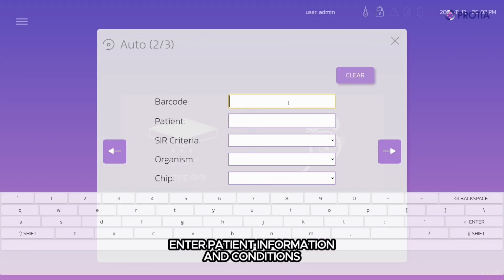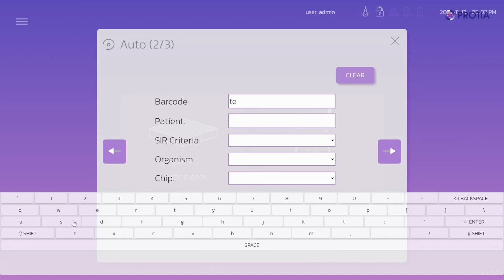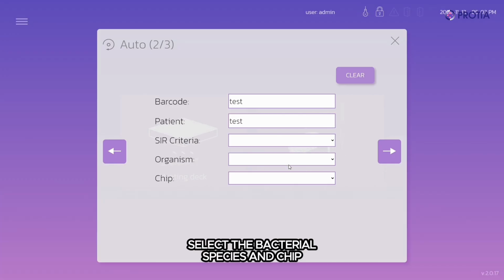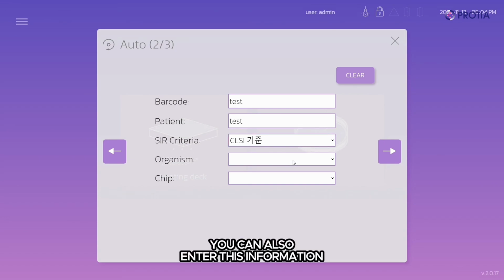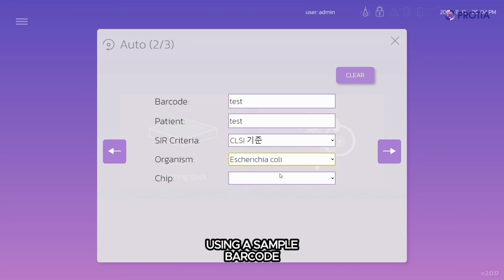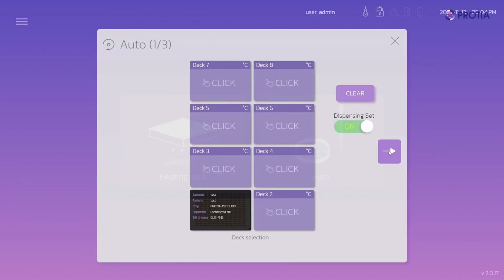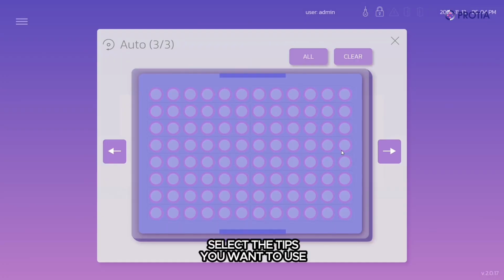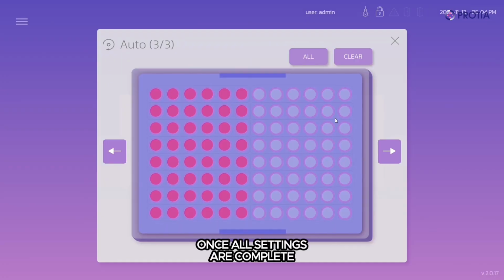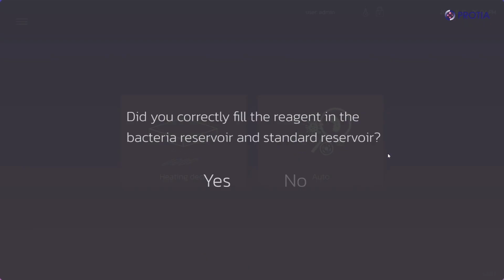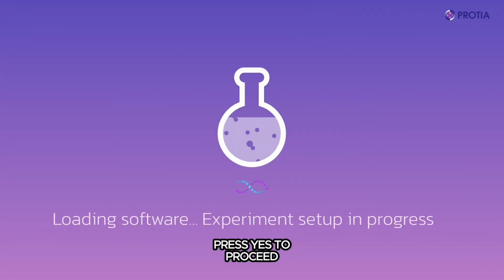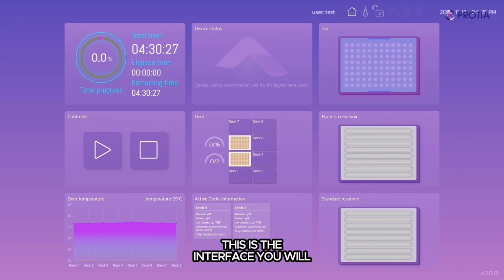Enter patient information and conditions. Enter the patient's name. Select SIR criteria. Select the bacterial species and chip type. You can also enter this information using a sample barcode. Select the PROTIA AST DL001 chip to use. Select the tips you want to use. Once all settings are complete, this message will appear. Please confirm your test and control samples. Press Yes to proceed. Once the settings are completed, this is the interface you will see on the equipment.